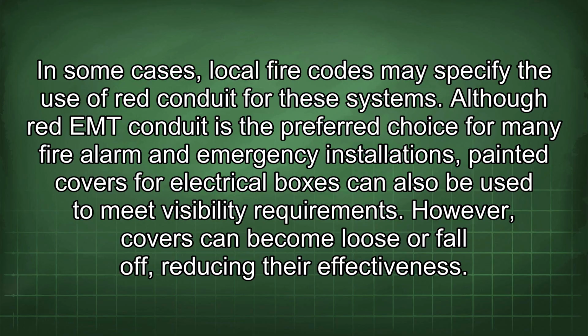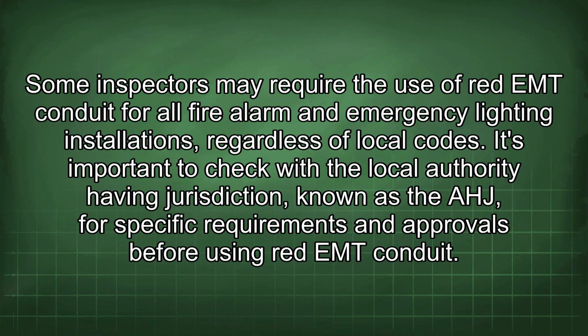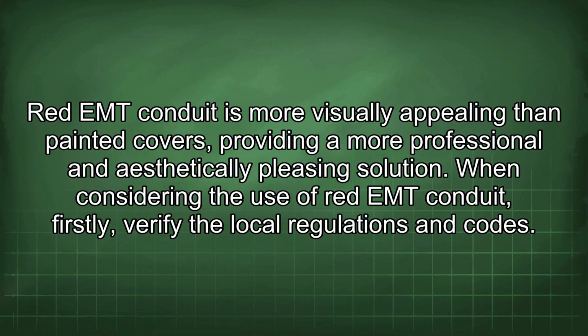Although red EMT conduit is the preferred choice for many fire alarm and emergency installations, painted covers for electrical boxes can also be used to meet visibility requirements. However, covers can become loose or fall off, reducing their effectiveness. Some inspectors may require the use of red EMT conduit for all fire alarm and emergency lighting installations, regardless of local codes. It's important to check with the local authority having jurisdiction, known as the AHJ, for specific requirements and approvals before using red EMT conduit. Red EMT conduit is more visually appealing than painted covers, providing a more professional and aesthetically pleasing solution.